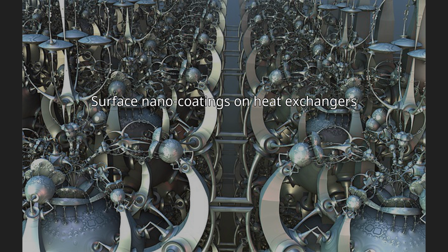It is possible that the nanoparticles act as small-scale fins, which are known to improve heat exchanger effectiveness. Since these nanoscale fins are small, the pressure drop is also much less compared to the pressure losses of a large-scale fin. This reduces the work requirements in pumping or compressing the fluid as it passes through the heat exchanger. The presence of surface roughness associated with nanoparticle deposits also promotes mixing, which directly affects convective heat transfer.